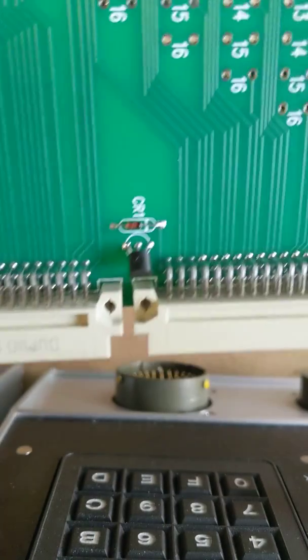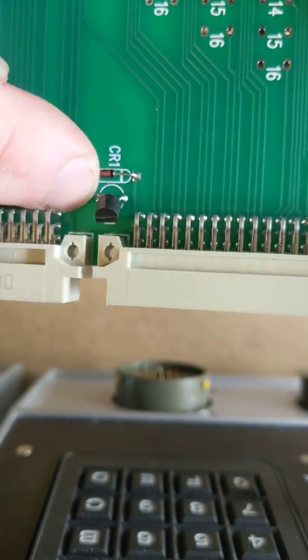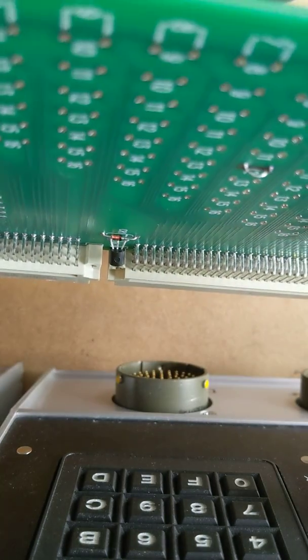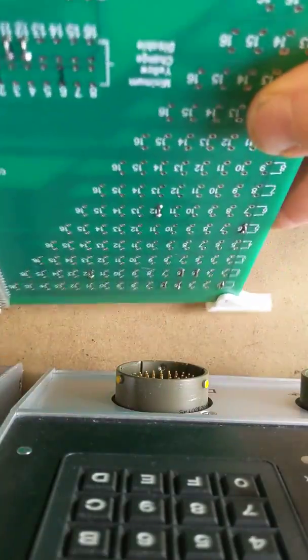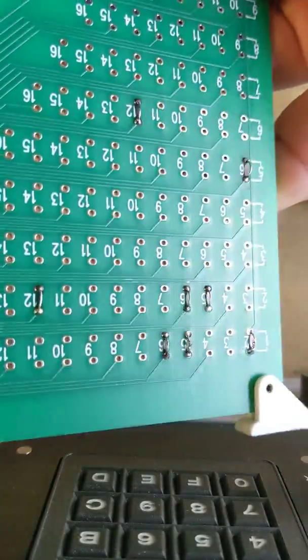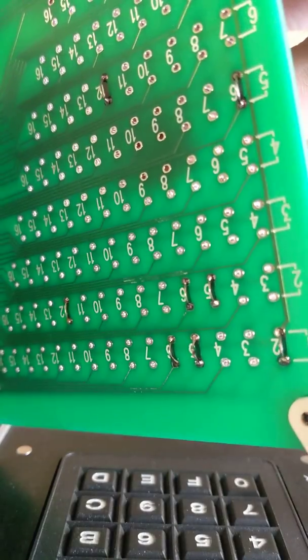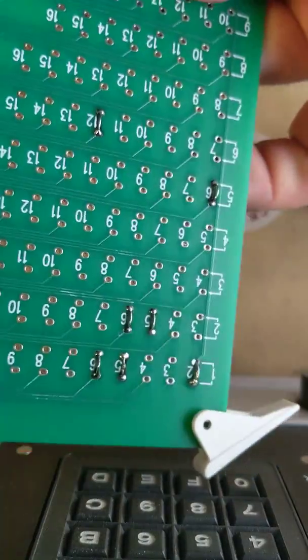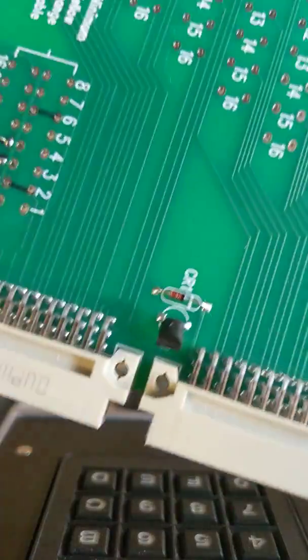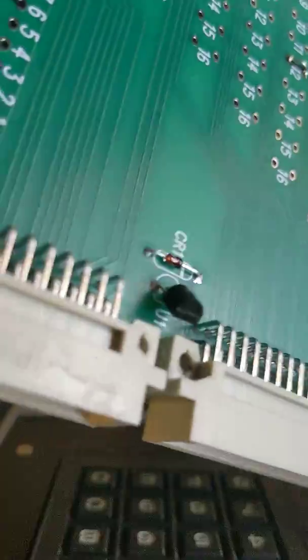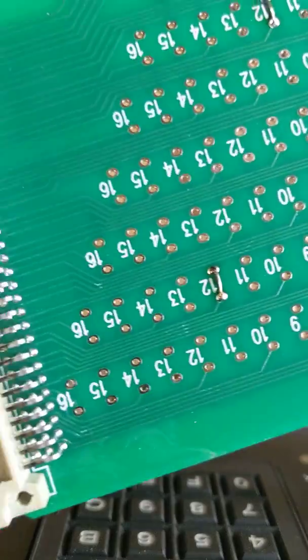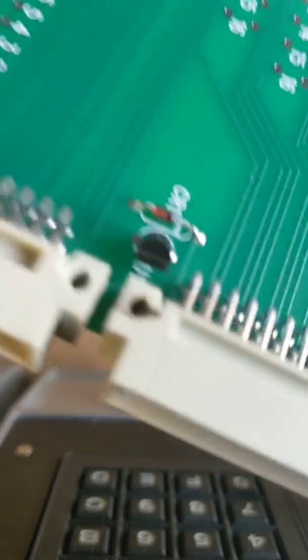And this particular card here has a memory on it. That's what this little chip is. And it will store the program, not only on here, but if you have a MMU set up for a flashing yellow arrow or anything, just an intersection. You can actually save that intersection here. And that's usually what we do the first time once we have it set up here in the lab and ready to go out, then we basically save it to the card. And that should be the deal.